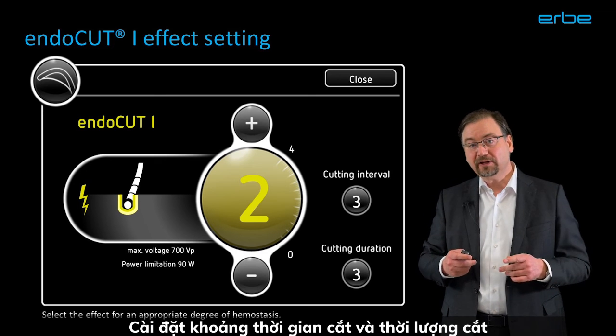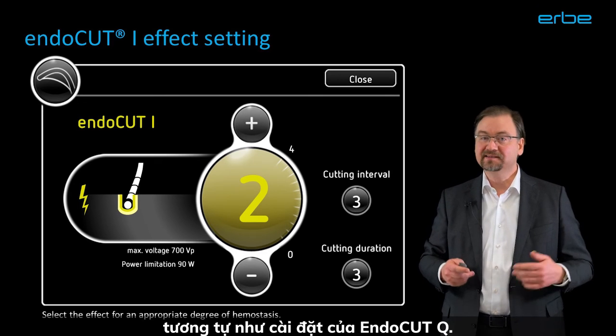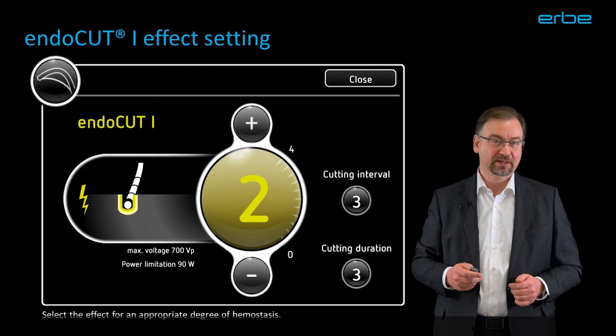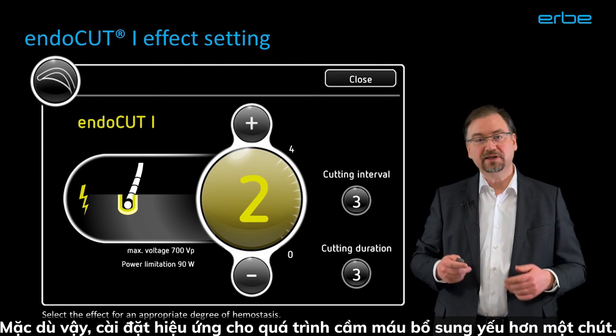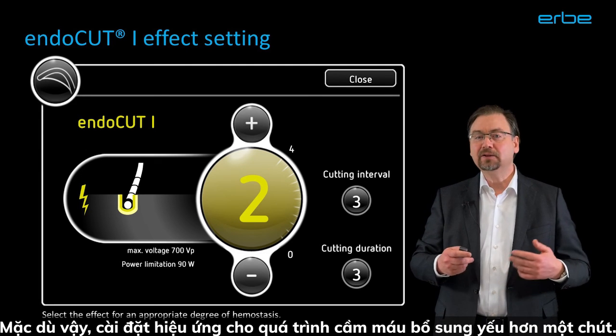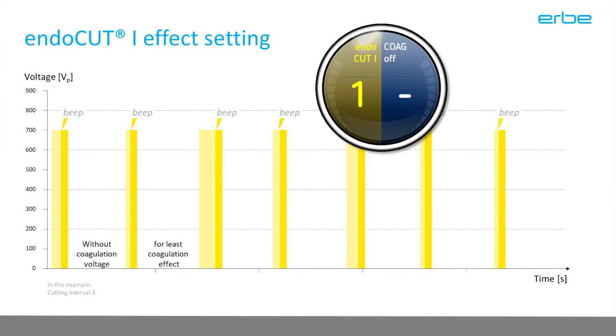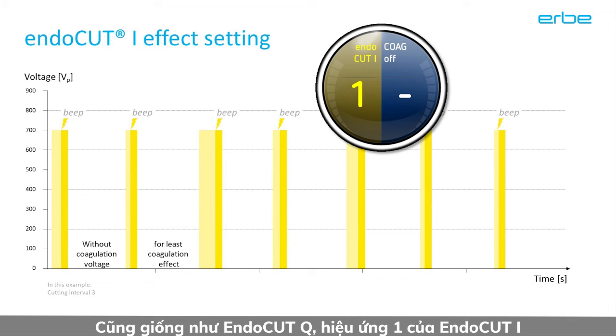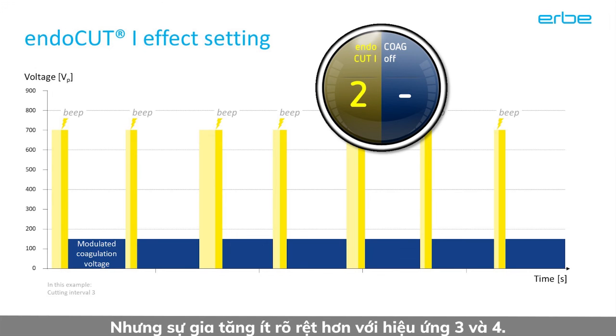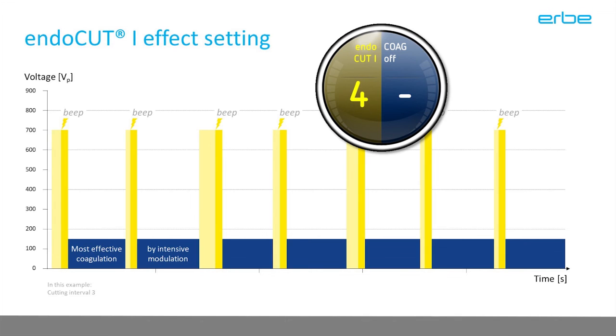The cutting interval and cutting duration settings are similar to those of EndoCut Q. The effect settings for the additional hemostasis are a little weaker though. Just as with EndoCut Q, effect 1 on EndoCut I is without additional coagulation phases in between the cutting cycles. But the increase is less pronounced with effect 3 and 4. Effect 3 and 4 just have a different waveform.